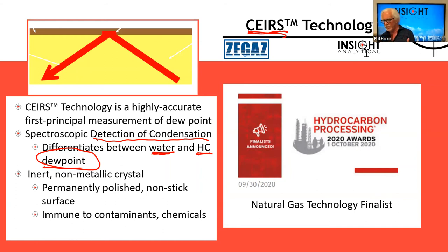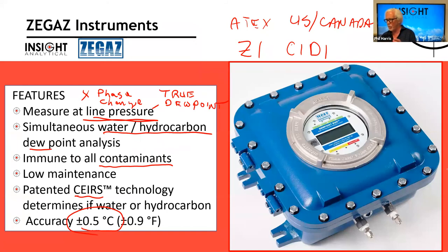So one of the nice things about this technology is that since it is Div 1, Zone 1, and it's a relatively small package, the analyzer is, I'm not even sure exactly, 15 inches by 15 inches, say 40 centimeters maybe. So we tend to mount these right out at the process point and keep the sample line really short. If it's a clean gas like natural gas, run it through eighth inch electropolished tubing, so we don't get absorption on the walls. And that lets us keep the response time for getting to the analyzer quite short. We'll be able to do a sample system that responds in less than a minute.